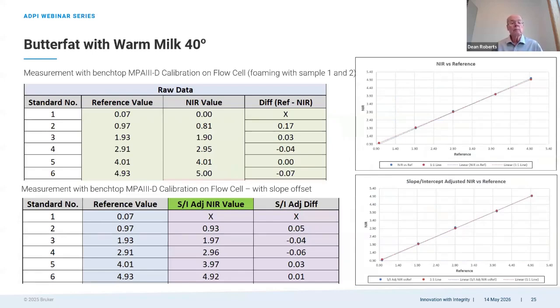Here's an example of what we got with the 40 degrees C. There was a little bit of a difference in the slope and offset. We didn't put the skim milk in there, and we did put the 1% in there. Then we show the results with the slope and offset. The 1% was still a little bit high, and the 2% was a little low, but we're right on there with the 3% through the 5% measurements. We had enough signal left that we think we probably could have gone up to 6% butterfat quite nicely with this. Next slide.